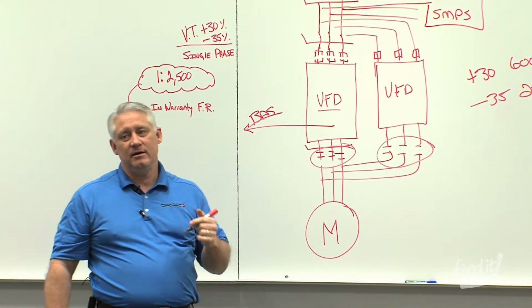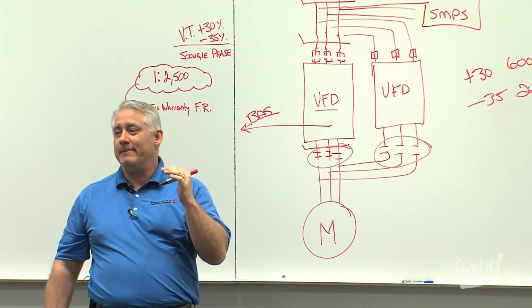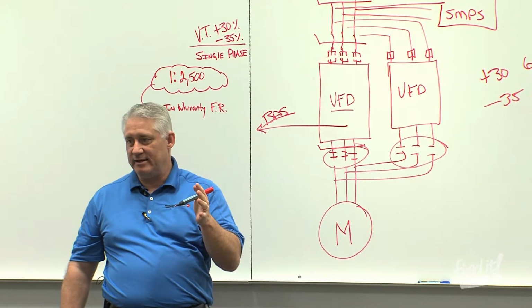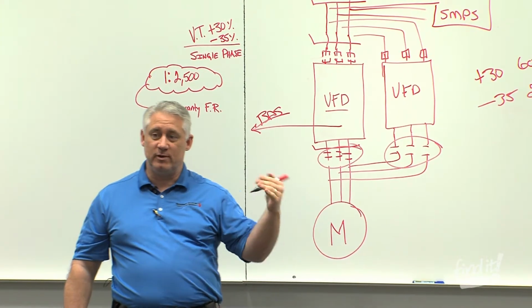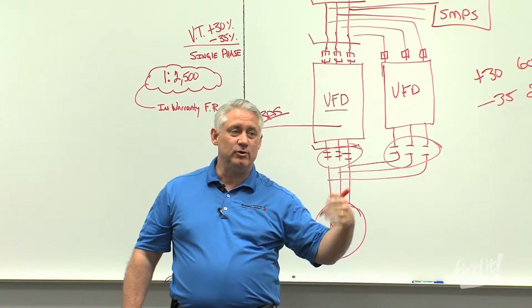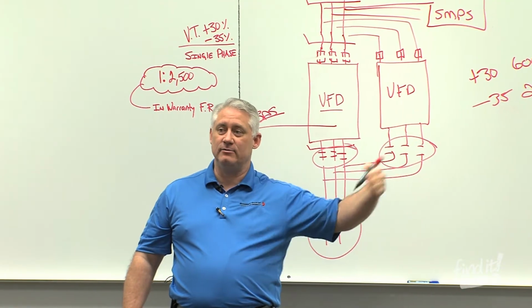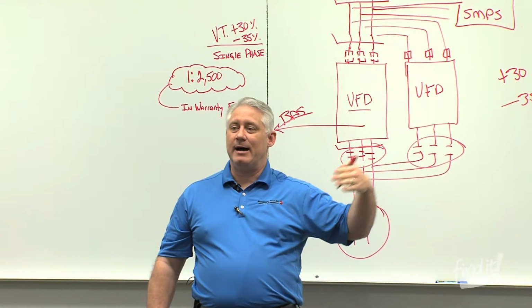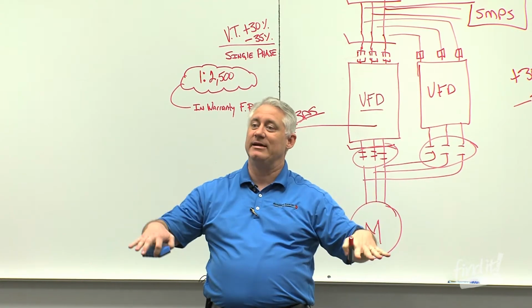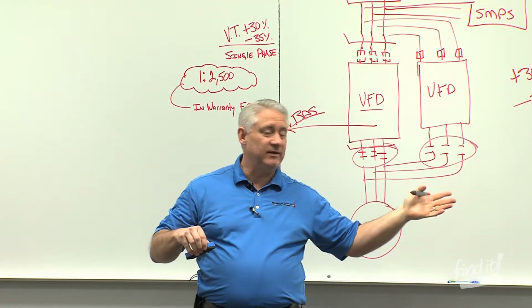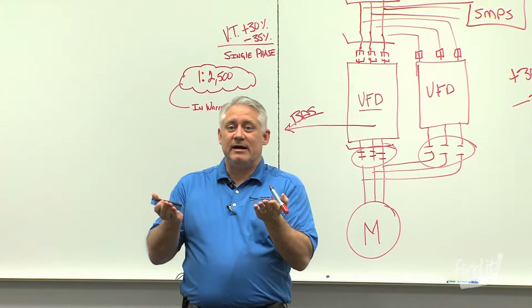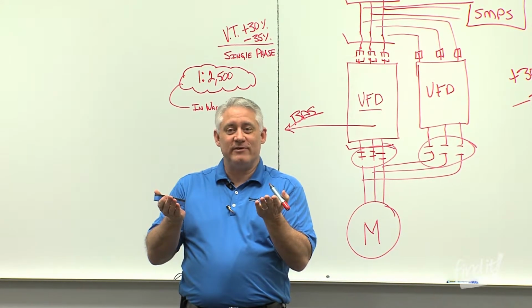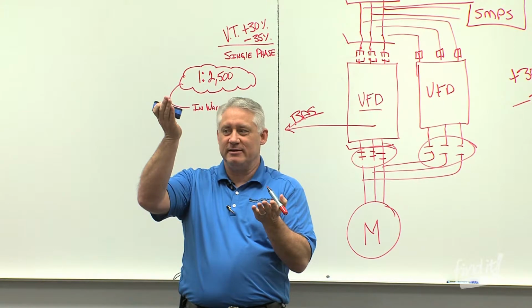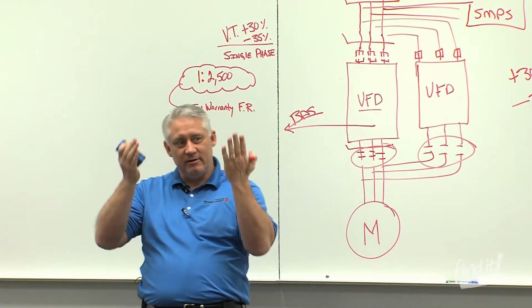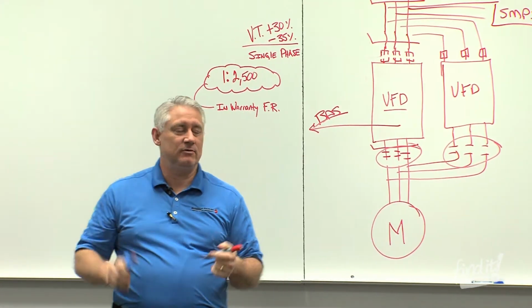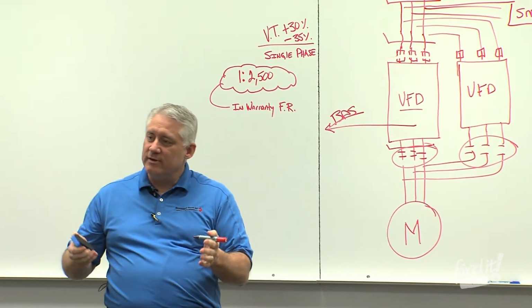We're also seeing much more frequently where we're operating multiple motors on the output of a VFD, and that can be done as well. We don't have to just run one drive with one motor. If we have a cooling tower with 3 cells and 3 identical motors, we can size that VFD to operate all those motors. Now they're all going to ramp up and down together, but guess what? Richard went through the affinity laws earlier. 2 cooling towers running at 50% speed is way more efficient than 1 cell running at 100% speed. So if we ramp these up and down together, we're going to see significant energy savings. So just some things that are new in technology.